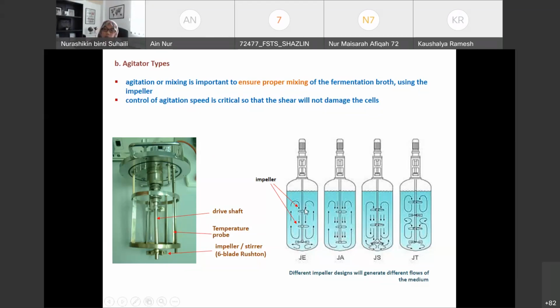If the impeller is not distanced properly, maybe it's too far or too close, there could be what we call a dead zone inside the reactor during the fermentation. A dead zone means that part is not mixing, so the media in that part is not circulated, or maybe the cells in that part are not circulated well. So it could lead to inefficiency of the fermentation.